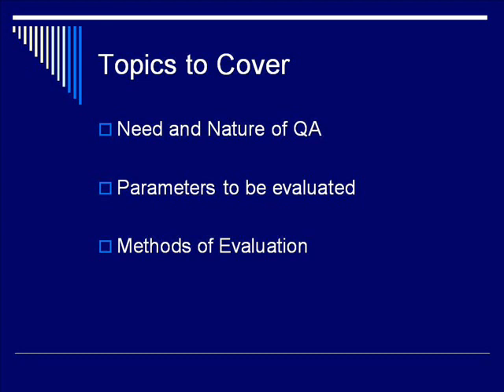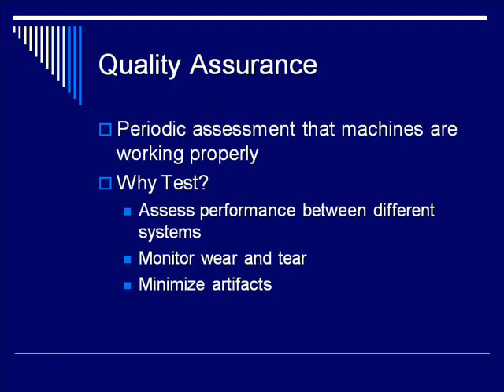The need and nature of QA is basically what is quality assurance and why do we need to do it. The parameters and the methods is what do we evaluate and how do we evaluate it. Quality assurance is a periodic assessment to make sure that your machines are still working properly. Ultrasound machines are very complicated, things can go wrong in a number of steps, and consistently testing things is a good way to see what is working, what isn't, and how to fix it.